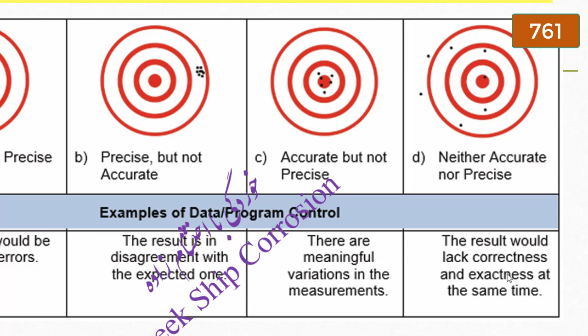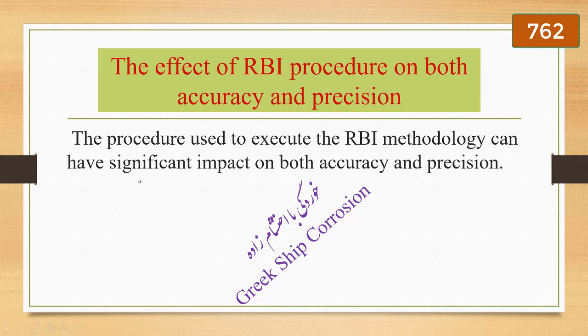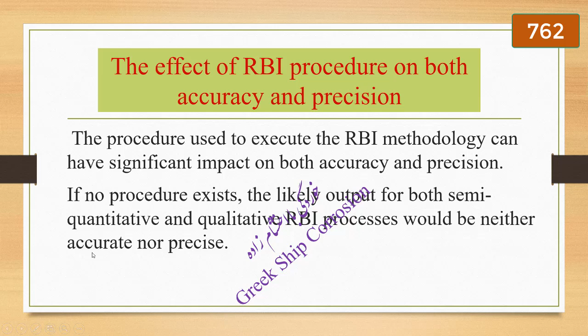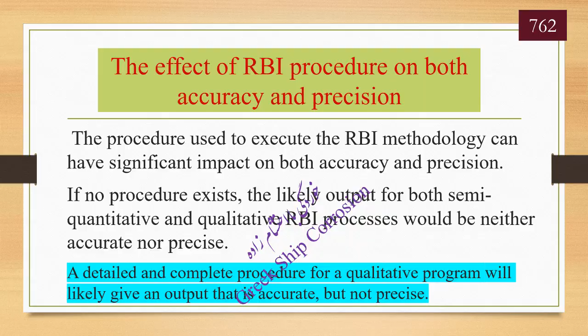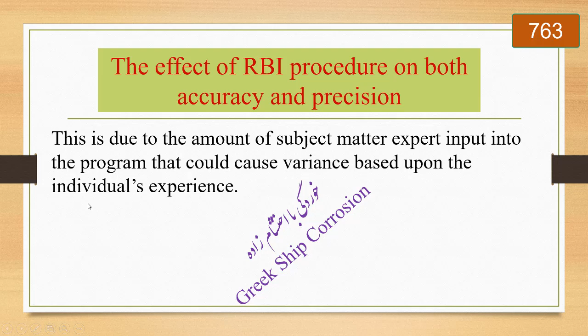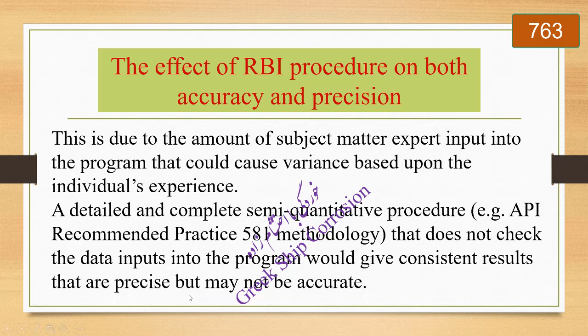The effect of RBI procedure on both accuracy and precision. The procedure used to execute the RBI methodology can have significant impact on both accuracy and precision. If no procedure exists, the likely output for both semi-quantitative and qualitative RBI processes would be neither accurate nor precise. A detailed and complete procedure for a qualitative program will likely give an output that is accurate but not precise. This is due to the amount of subject matter expert input into the program that could cause variance based upon the individual's experience. A detailed and complete semi-quantitative procedure, for example, API Recommended Practice 581 methodology, that does not check the data inputs into the program would give consistent results that are precise but may not be accurate.